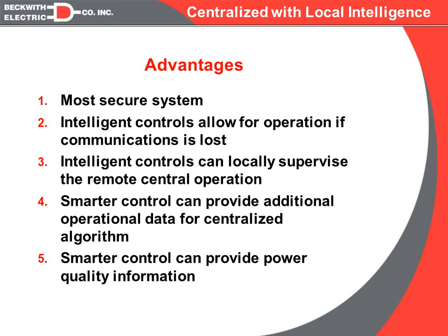So if we determine that we never want the voltage to be above 126, and a capacitor control on an open capacitor bank receives a command to close the bank, and in doing so that'll drive the voltage above 126, in the one-way paging scheme, it's going to close the bank regardless. In this scheme, it's not going to close the bank.